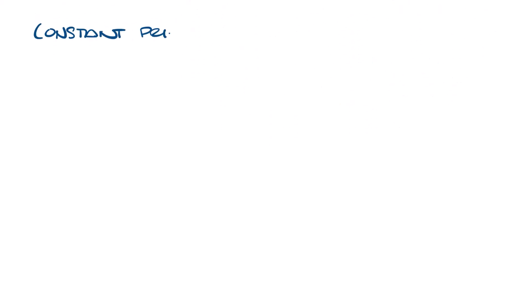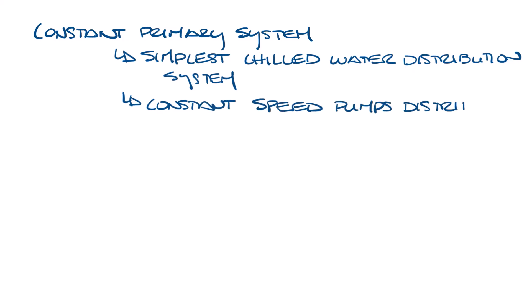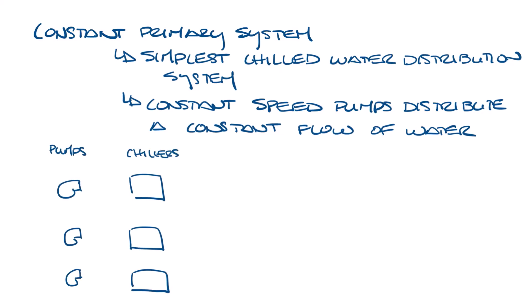Originally, there was the constant primary circulation system. It's the simplest chilled water distribution system. In it, constant speed pumps distribute a constant flow of water at all times. So let's draw this. Let's say we have three pumps, three chillers, and three air handlers.